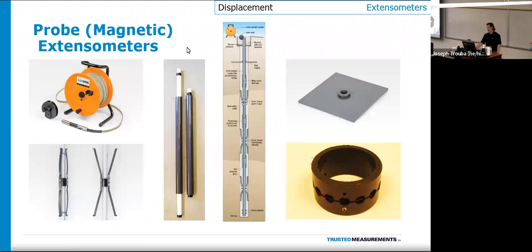This is what it would look like. So the top left here is a reed switch probe. These would be spider magnets, unactivated and then activated. So they usually go down unactivated. You get to your point of concern or measurement, and you can activate the spider magnet. It'll basically expand into your borehole wall, and they can be folded that way. This is a telescopic coupling, plate magnet, and then your datum ring. This is how it would look down the hole, so different spider magnets, your datum magnets down here. And so you can lower your reed switch probe and take your measurements down the axis too.